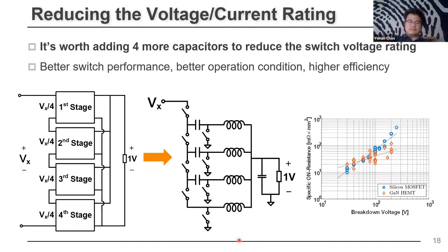This is our final design for the 48 volt to 1 volt high current CPU voltage regulator. First we put a pre-conversion stage, which converts the 48 volt input to a 24 volt intermediate bus. The second stage is the circuit mentioned previously, with series input and parallel output configuration. The input of the second stage is 24 volt to 1 volt, so the voltage conversion ratio is 24 to 1, but the equivalent input voltage of each switch is only 6 volts. This allows us to use low breakdown voltage switches with lower switching voltage, so switching performance and overall system efficiency are both improved.